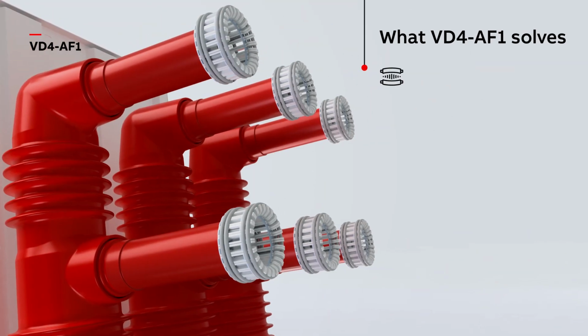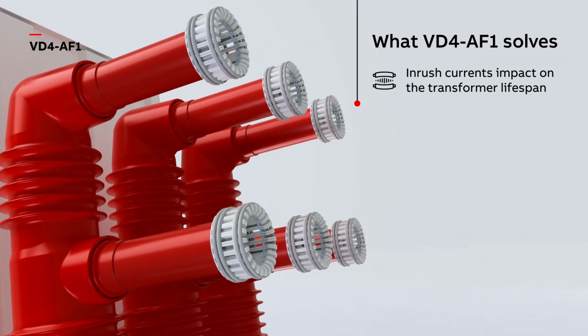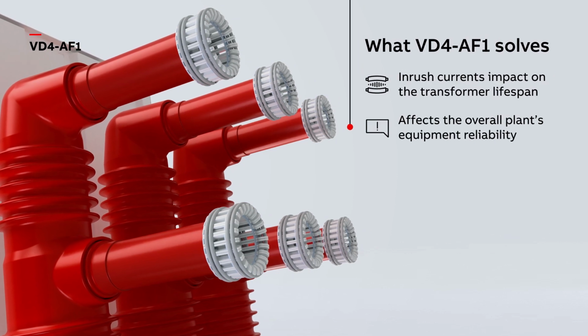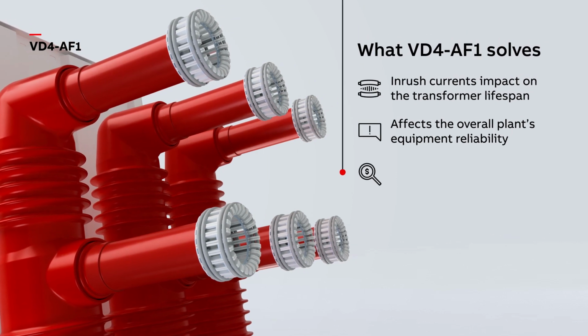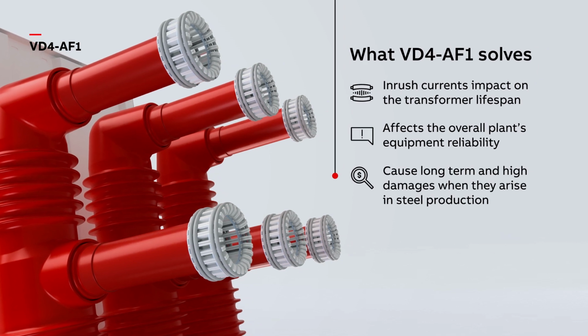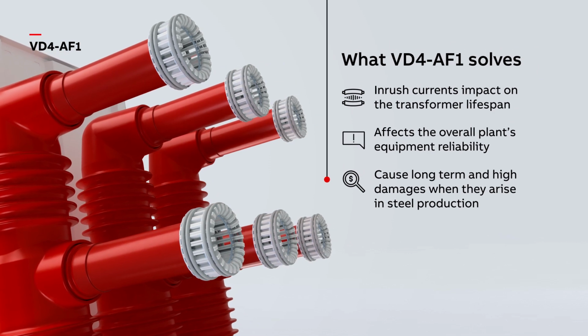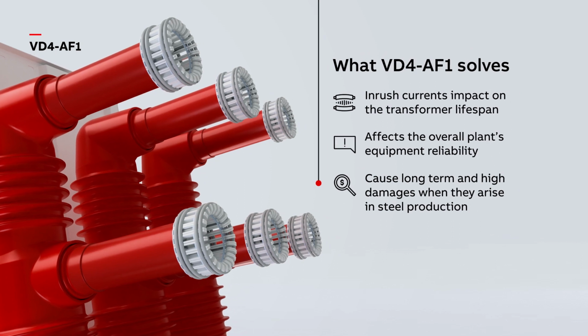Inrush currents are the electrical phenomena affecting the reliability and the lifespan of any transformer in a steel furnace application, impacting on all the assets connected to the same plant, causing long-term and huge damages when they arise.